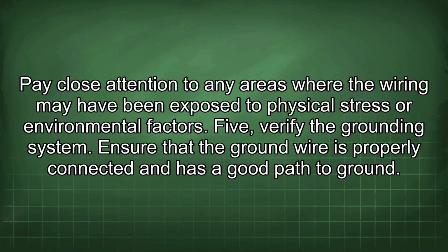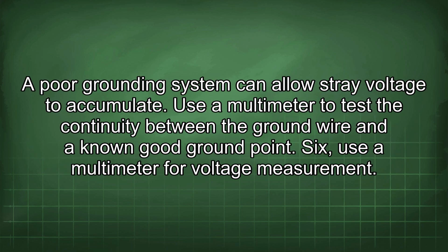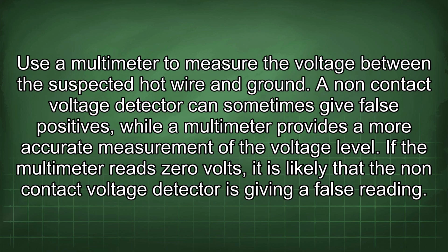5. Verify the grounding system. Ensure that the ground wire is properly connected and has a good path to ground. A poor grounding system can allow stray voltage to accumulate. Use a multimeter to test the continuity between the ground wire and a known good ground point. 6. Use a multimeter for voltage measurement. Use a multimeter to measure the voltage between the suspected hot wire and ground. A non-contact voltage detector can sometimes give false positives, while a multimeter provides a more accurate measurement of the voltage level. If the multimeter reads 0 volts, it is likely that the non-contact voltage detector is giving a false reading.